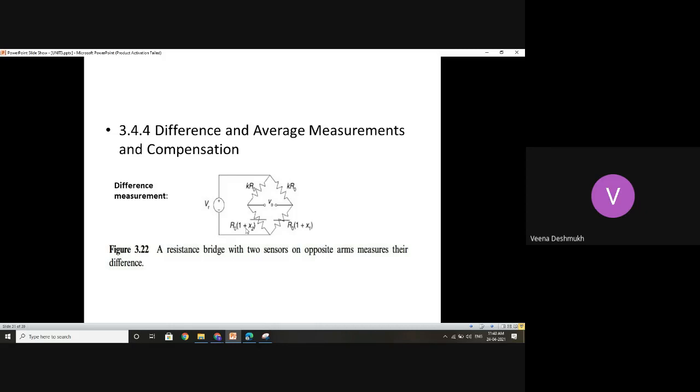Because of the proportional variations we discussed, practically over the same range we have seen in RTDs, in some regions the linearity does not exist. So if the calibrations are done in the non-linear region, considering a linear variation, then all these calculations or the calibrations go wrong.